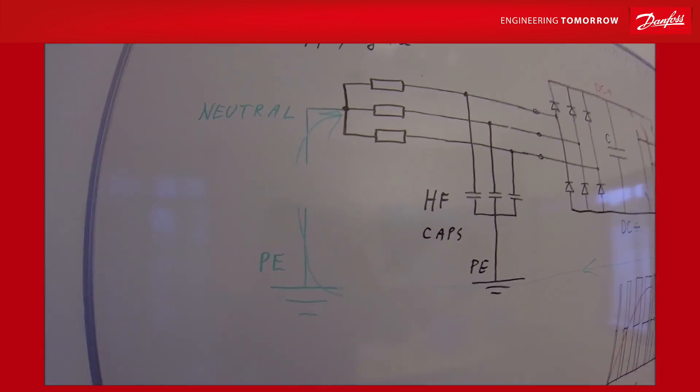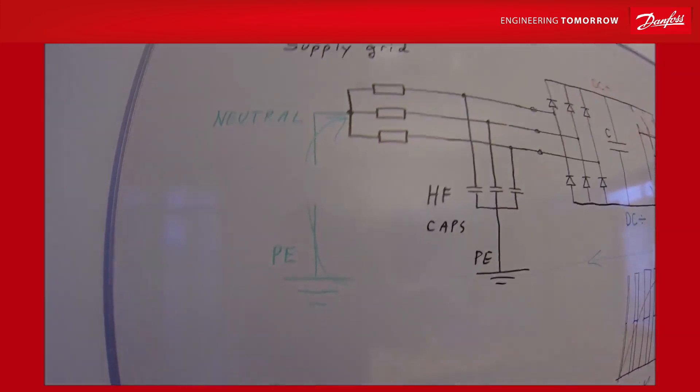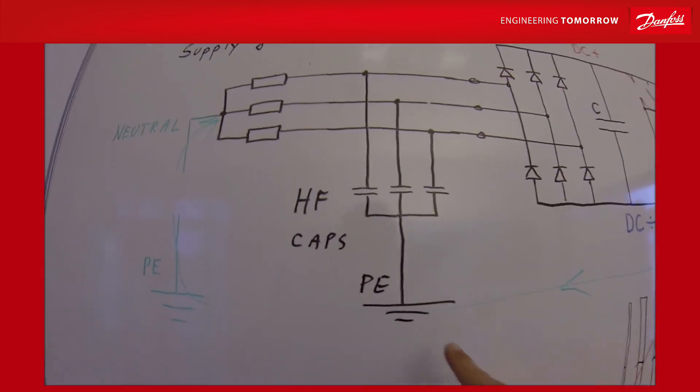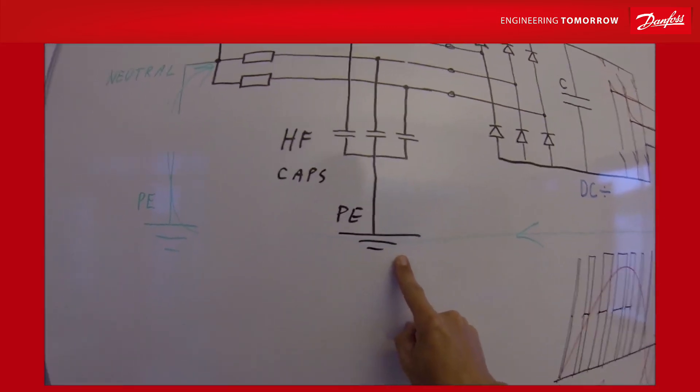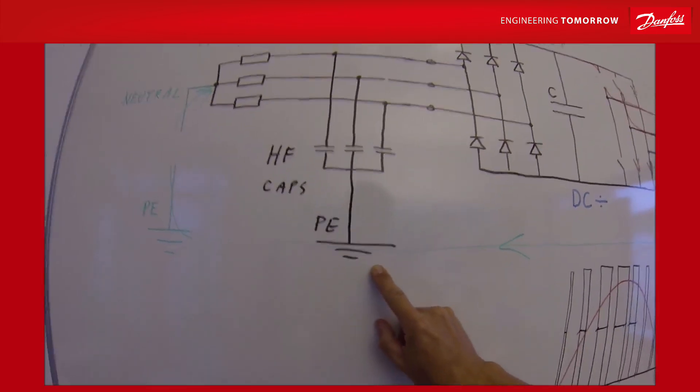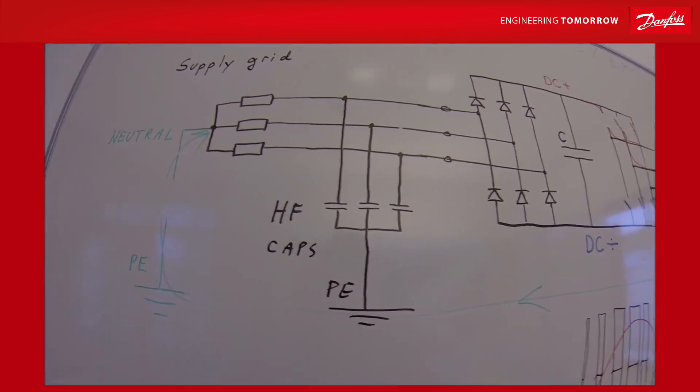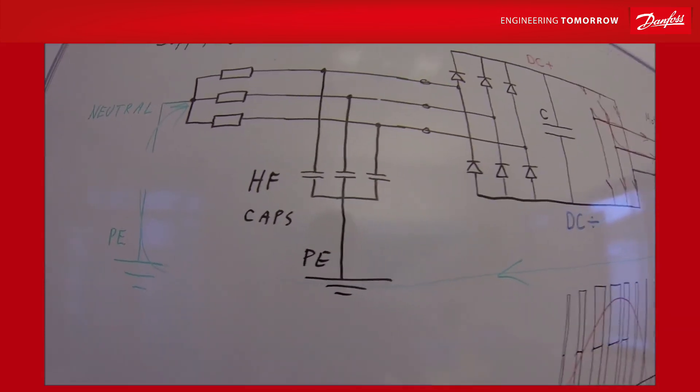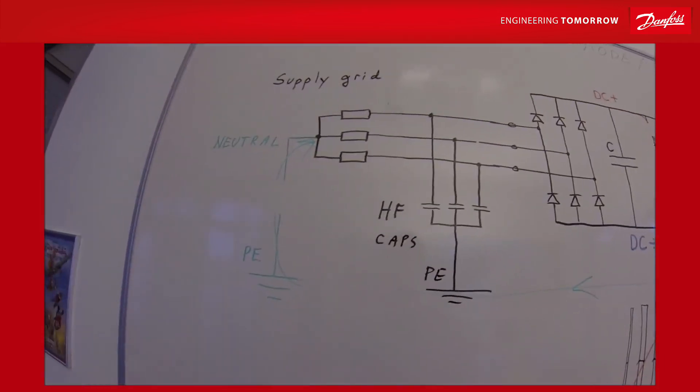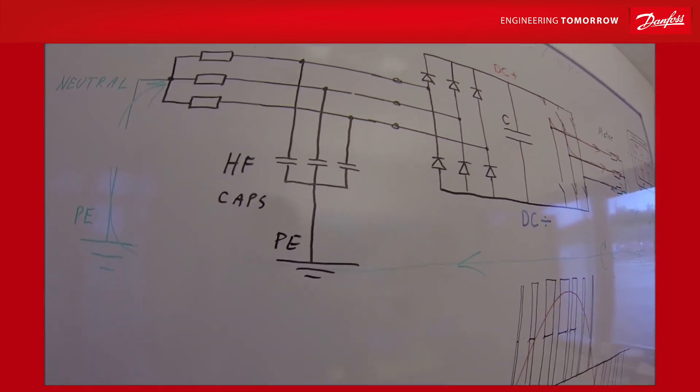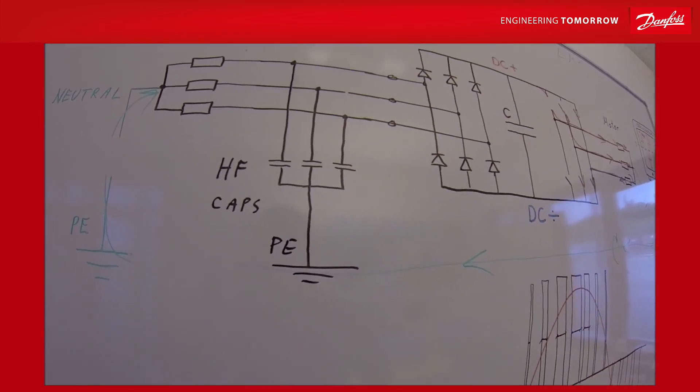The high frequency caps can be used when you have a grounded system like in buildings onshore, or when you have TNS and TN kind of supply grids. But onboard ships, this might be a problem because the ground is floating. You have a so-called IT power system. Then you are not allowed to use these HF caps directly to the protective earth. So it is a little bit different between onshore installations and offshore installations in maritime industry.